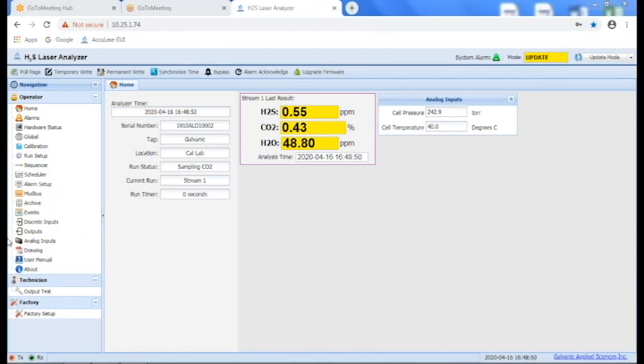Then when we measure H2O, or water vapor, we turn the H2S laser off and turn the H2O laser on, and that laser is tuned to an absorbance feature of H2O. In this way, we get a sequential measurement of the three different components. Say we do it based on a 10-second cycle; that gives you a 30-second cycle of measurement of the three components. So you get an update every 30 seconds to a minute for all the components.